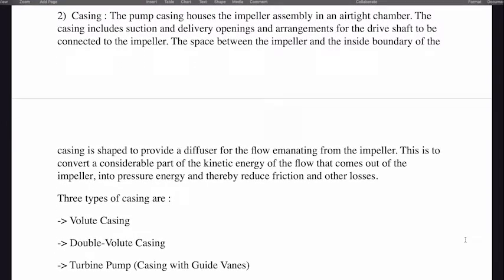The pump casing houses the impeller assembly in an air-tight chamber. The casing includes suction and delivery openings and an arrangement for the drive shaft to be connected to the impeller. The space between the impeller and the inside boundary of the casing is shaped to provide a diffuser for the flow emanating from the impeller, converting kinetic energy into pressure energy and thereby reducing friction and other losses. Three types of casings are available: volute casing, double volute casing, and turbine pump casing with guide vanes.